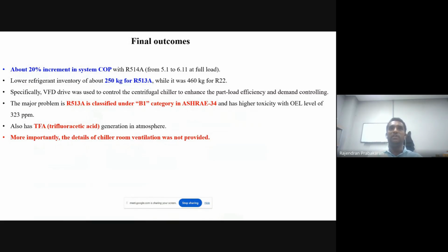The specific advancement in this kind of facility is that they used a variable frequency drive controlled centrifugal chiller to enhance the part load efficiency and demand cooling controls. However, this refrigerant also has a TFA issue. More importantly, this refrigerant is classified under B1. B1 means no flammability, but highly toxic. So there should be proper ventilation. But in this case study, they have not provided details about the chiller room ventilation.